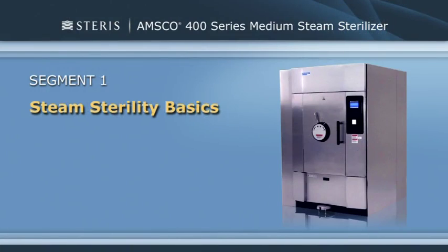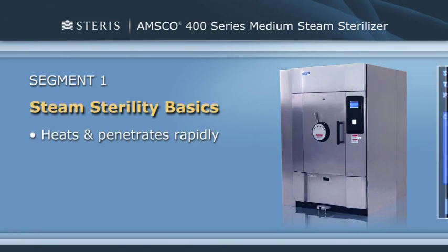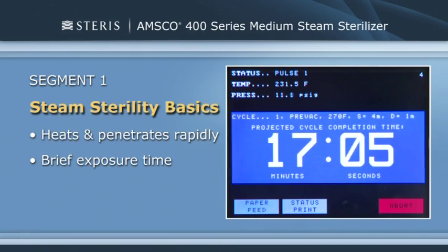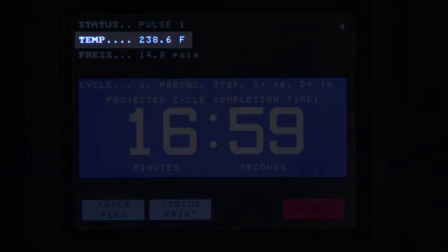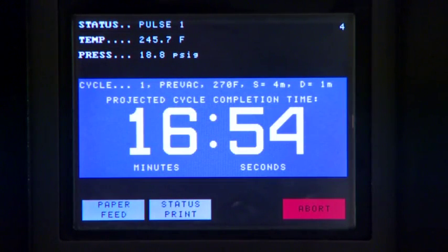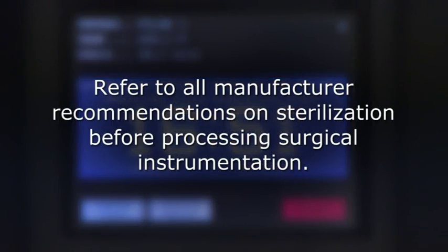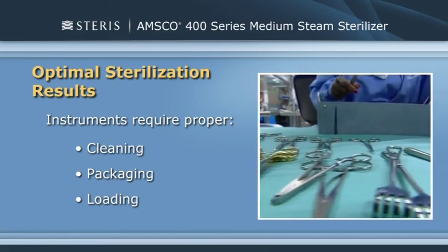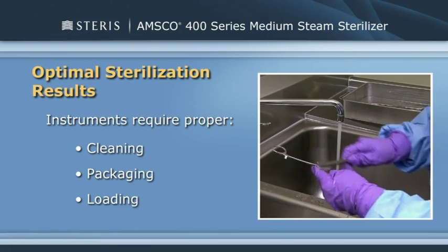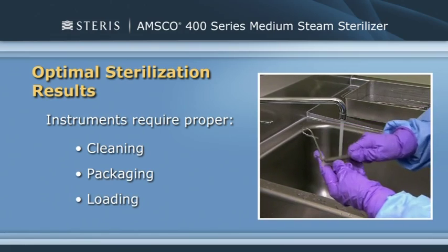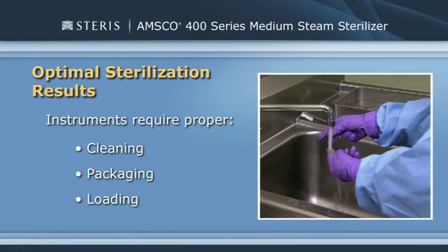Steam sterilization is the most cost-effective and dependable sterilization method available for surgical instrumentation. Steam heats and penetrates rapidly, requires brief exposure time, is non-toxic, and leaves no residues. Because of the high temperatures generated during this process, surgical instruments that are heat and moisture sensitive cannot be sterilized with steam. Please refer to all manufacturer recommendations on sterilization before processing surgical instrumentation. Steam sterilization relies on steam reaching all instrument surfaces. Therefore, proper cleaning, packaging, and loading of the instruments are vital to achieve optimal sterilization results.